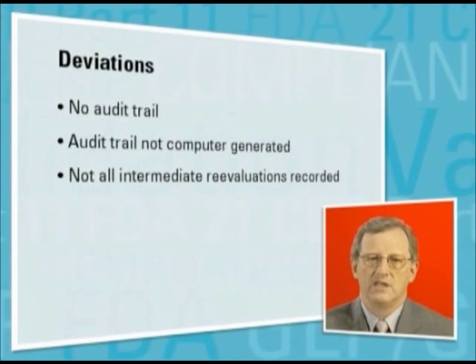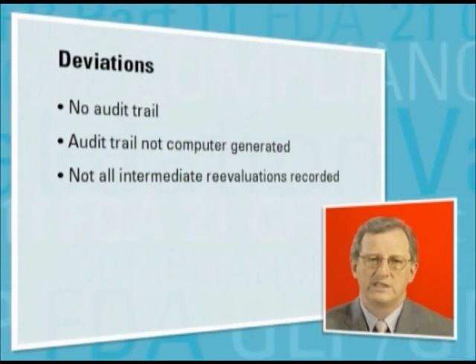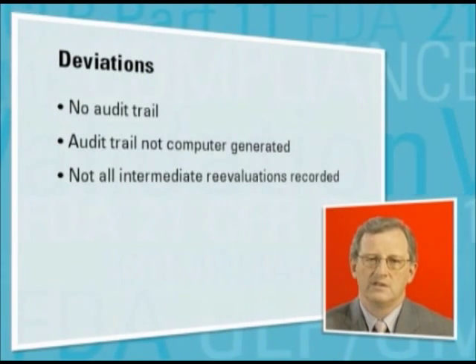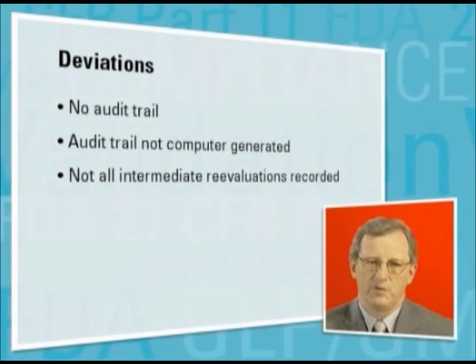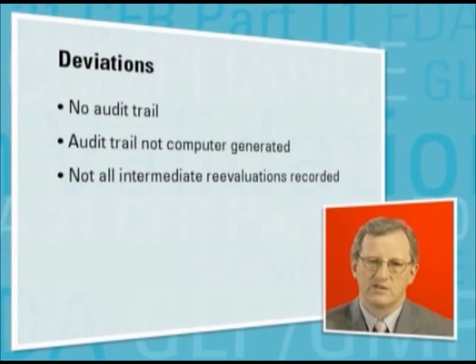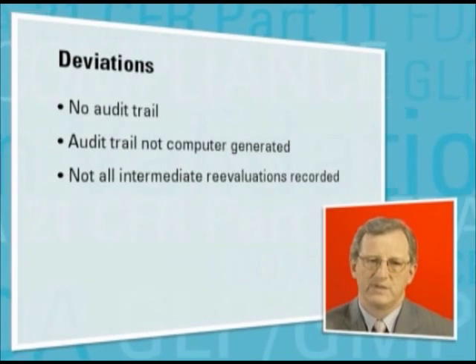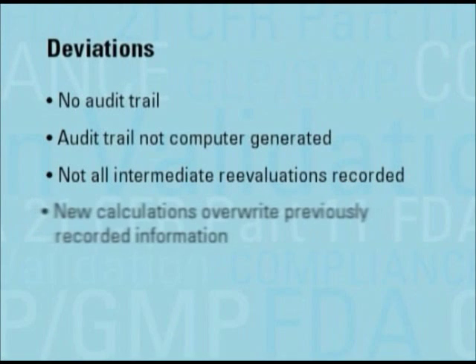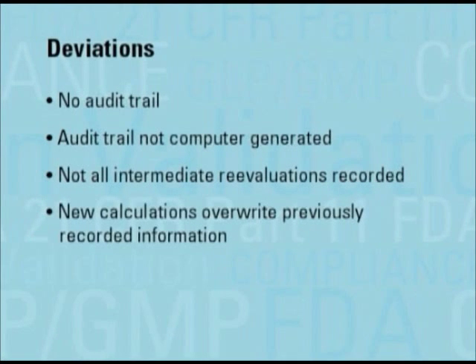In one of the 483s, we found a comment that it was not possible to determine how many times a chromatogram had been integrated. Another comment was that previously recorded information had been overwritten.